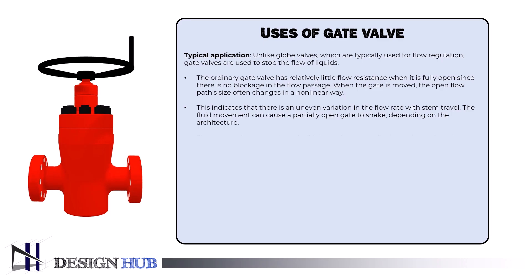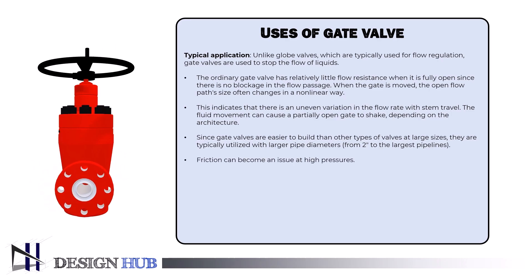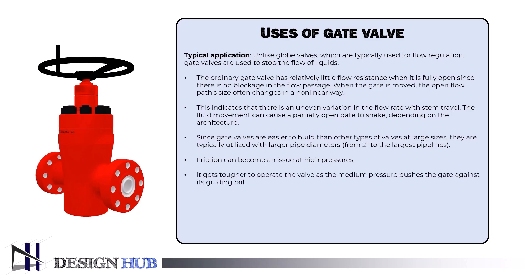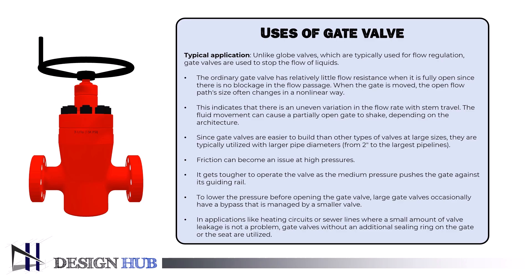Depending on the architecture, the fluid movement can cause a partially open gate to shake. Since gate valves are easier to build at large sizes, they are typically utilized with larger pipe diameters, from two inches to the largest pipelines. Friction can become an issue at high pressures. Large gate valves occasionally have a bypass managed by a smaller valve to lower pressure before opening. Gate valves without an additional sealing ring are utilized in applications like heating circuits or sewer lines where a small amount of leakage is not a problem.